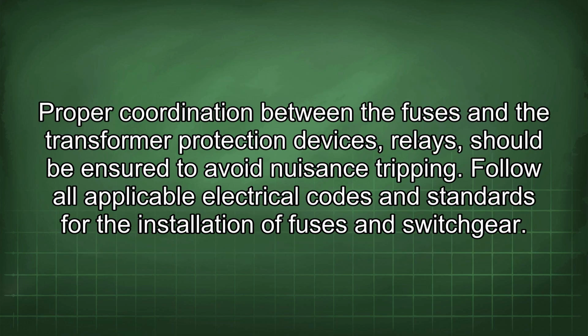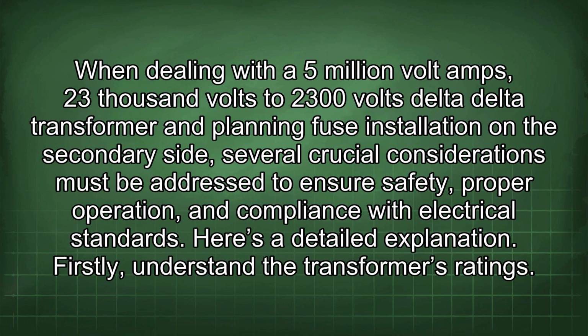Proper coordination between the fuses and the transformer protection devices, relays, should be ensured to avoid nuisance tripping. Follow all applicable electrical codes and standards for the installation of fuses and switchgear. When dealing with the 5 million volt amps, 23,000 volts to 2300 volts delta-delta transformer and planning fuse installation on the secondary side, several crucial considerations must be addressed to ensure safety, proper operation, and compliance with electrical standards.